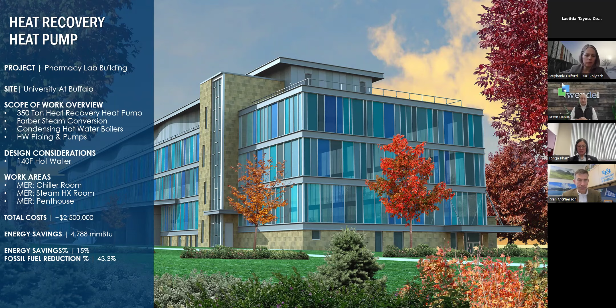Another great opportunity for heat recovery is finding simultaneous heating and cooling loads. Many college campuses and institutions may have a load profile where hot water is used all year, including summertime. How do you know hot water or heating is used in summer? Think dehumidification. Some areas of Canada have higher dehumidification loads in summer. If you have labs or collection areas, you're using hot water energy in summer to help dehumidify.